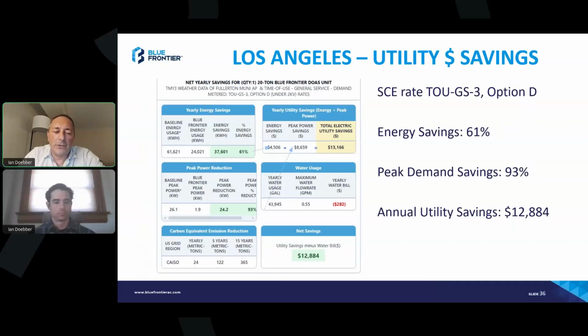To give a sense of the magnitude of water used: in Los Angeles, for a 20-ton unit, it's about 44,000 gallons annually. That represents the annual water consumption of a household with 1.5 people, average US—we did the math. So it's not a huge quantity of water; there is some, but it's relatively minor compared to other technologies.